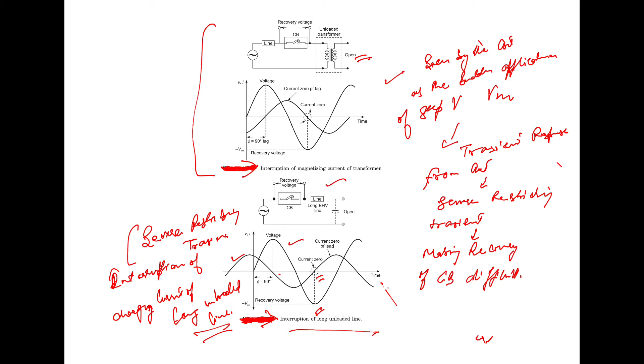In this case the current leads the voltage by almost 90 degrees, because it is a charging current. At the moment of current zero, the instantaneous value of supply voltage is almost the full peak voltage, and as in the previous case, this is bound to cause a severe re-striking transient. So we have the severe re-striking transient in this case also.